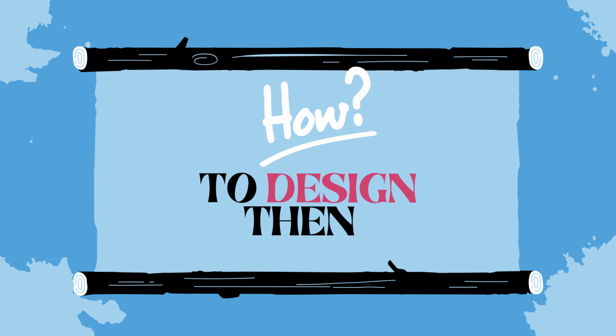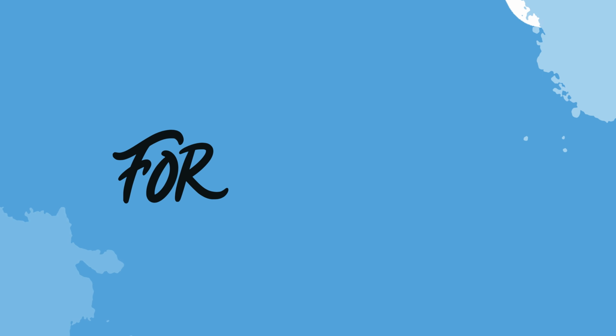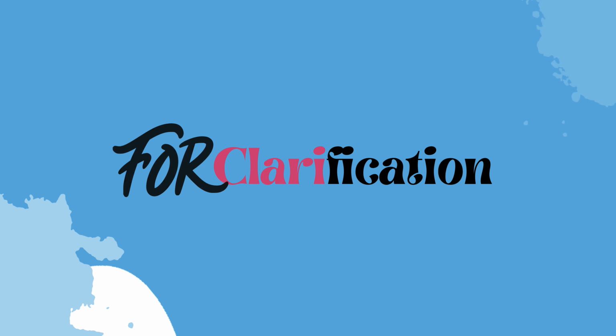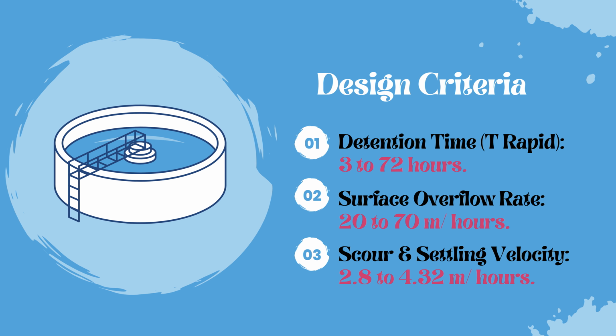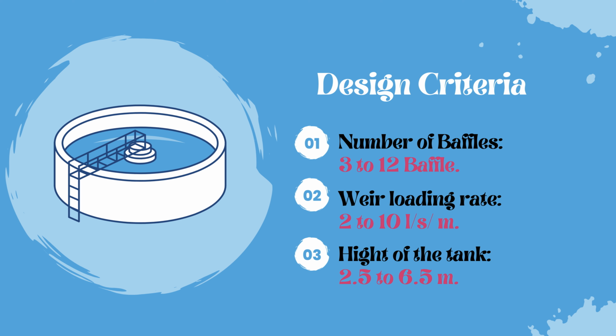But how do we design it? For clarification, we must consider several factors, including detention time, normally between 3 to 72 hours. Surface overflow rate, ranging from 20 to 70 meters per hour, and scour and settling velocity should be considered. Additionally, baffles, weir loading rate, and tank height are critical considerations.